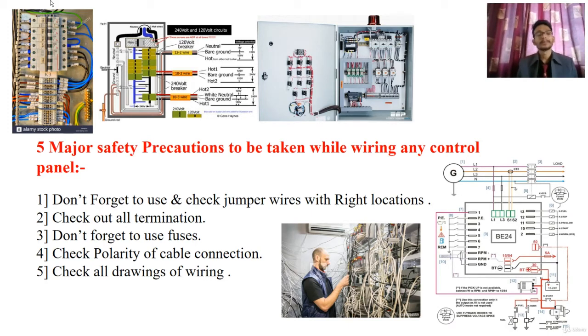First important thing is, don't forget to use and check the jumper wires with the right location. Many times in a control panel, jumper wires connect the whole system together. This can be done very easily with the help of jumper bars. The problem is that all these jumper bars are hidden inside the terminal box, so they can easily go unnoticed. Hence a loose connection or other insulation failures may result in open circuit or short circuit faults, and this power signal may cause a failure in the overall system, or a cable connection may lose some important signals to the PLC, because of which processing cannot be done in the proper way. So don't forget to use and check the jumper wires with the right location.